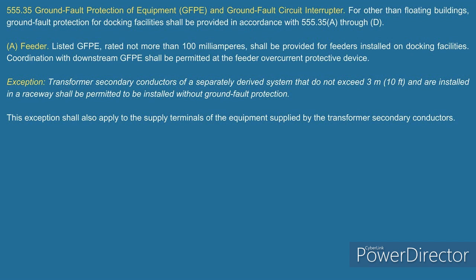First, I want to bring a point up here. He says at a point where it receives its supply is the outlet, and then he says at the receptacle, like if you were cord and plug connecting it. Well, first of all, a receptacle is a device. It's not an outlet. There's a reason that we have a definition for a receptacle outlet, which is the box, and then you have a definition for a receptacle. The outlet is the box. And that's why these terms are going to matter when we're looking at this.